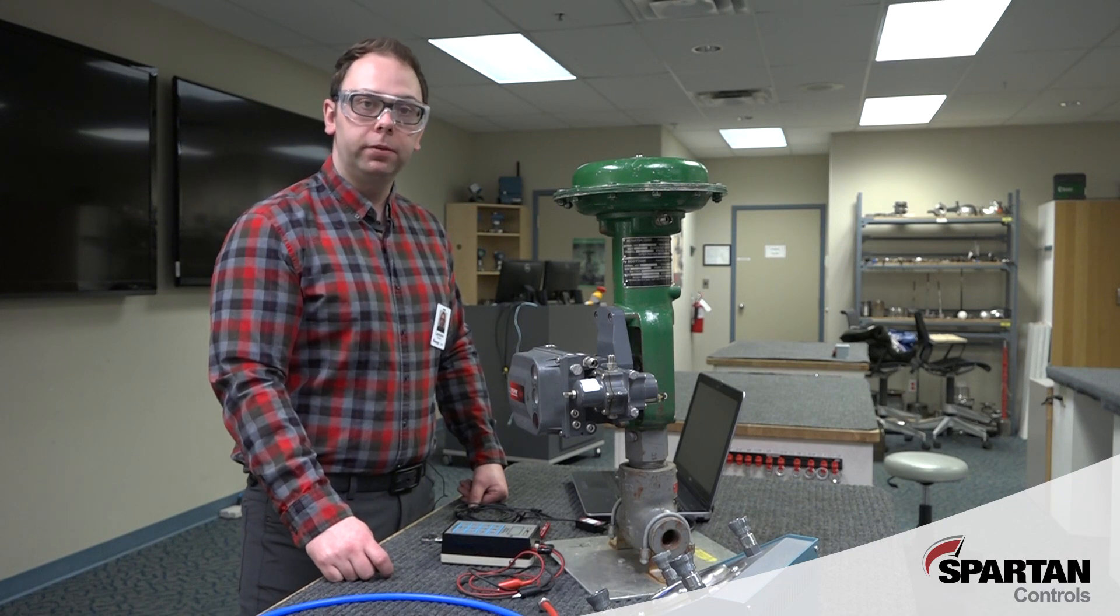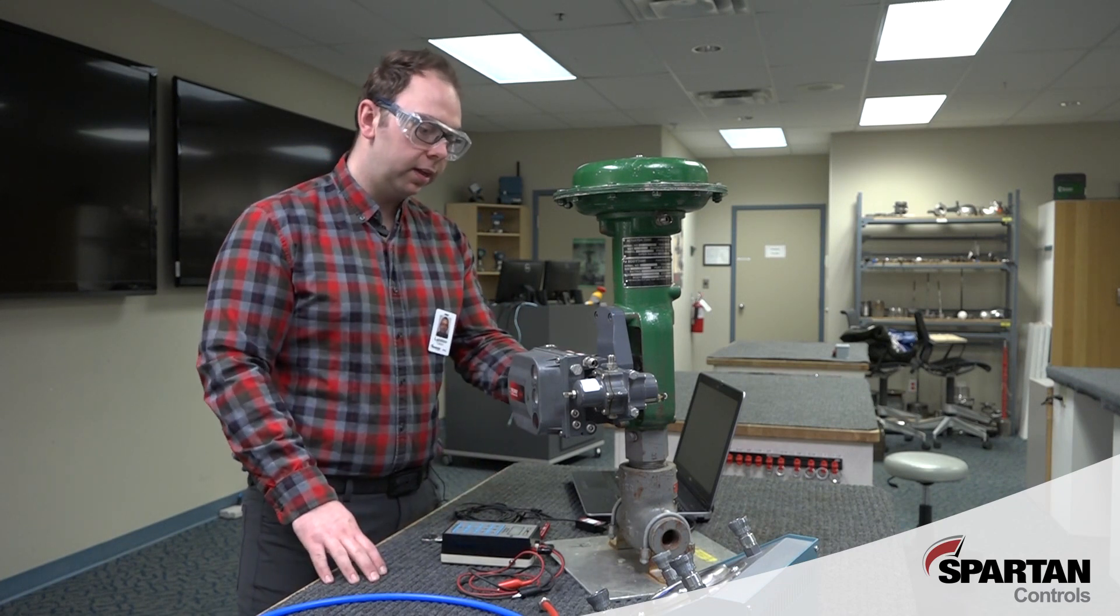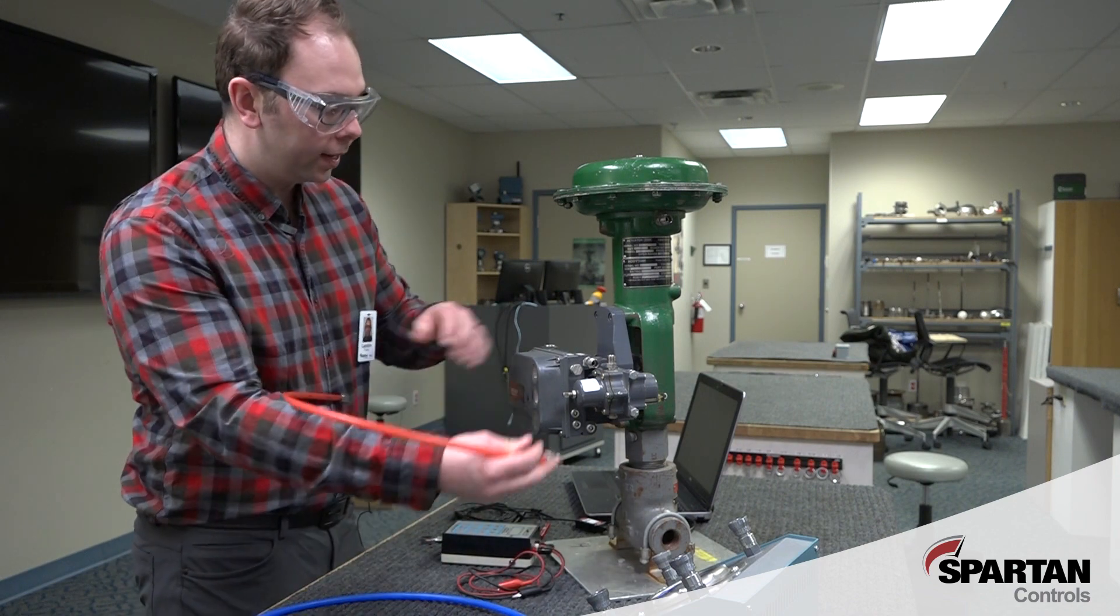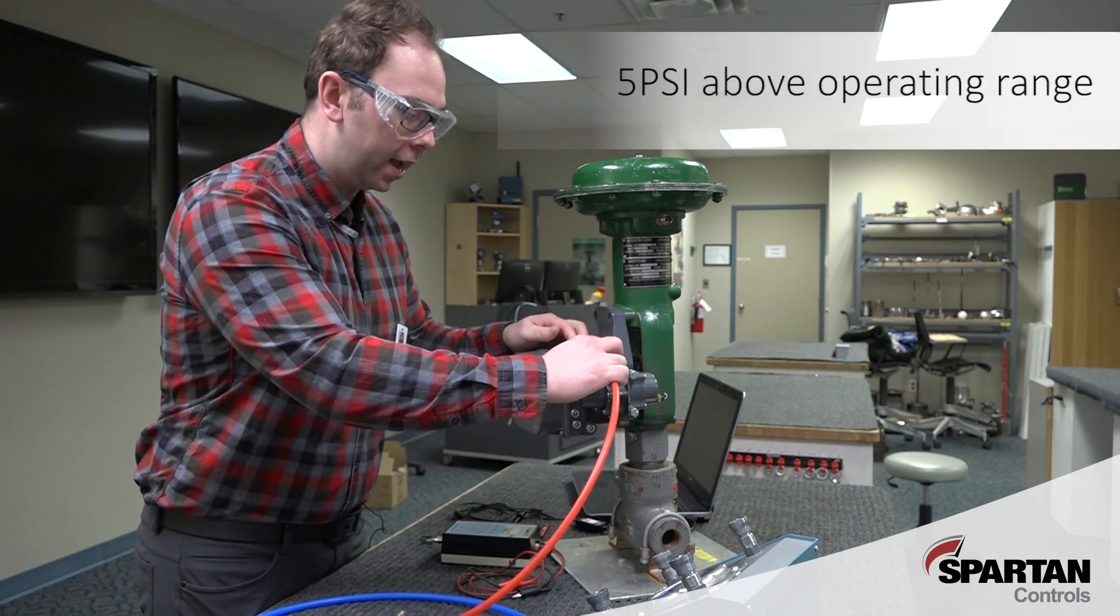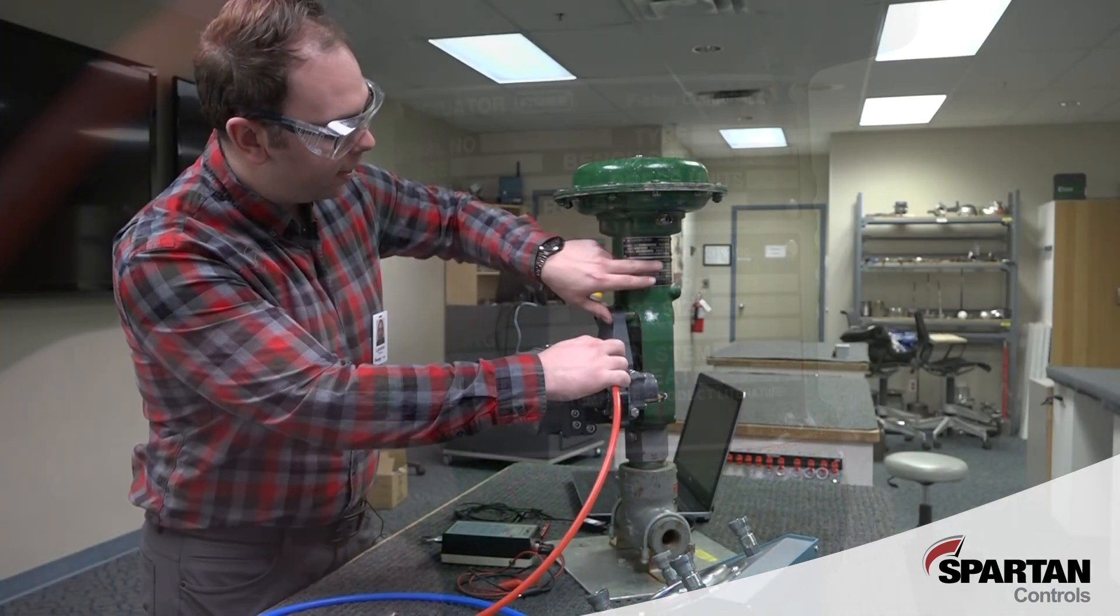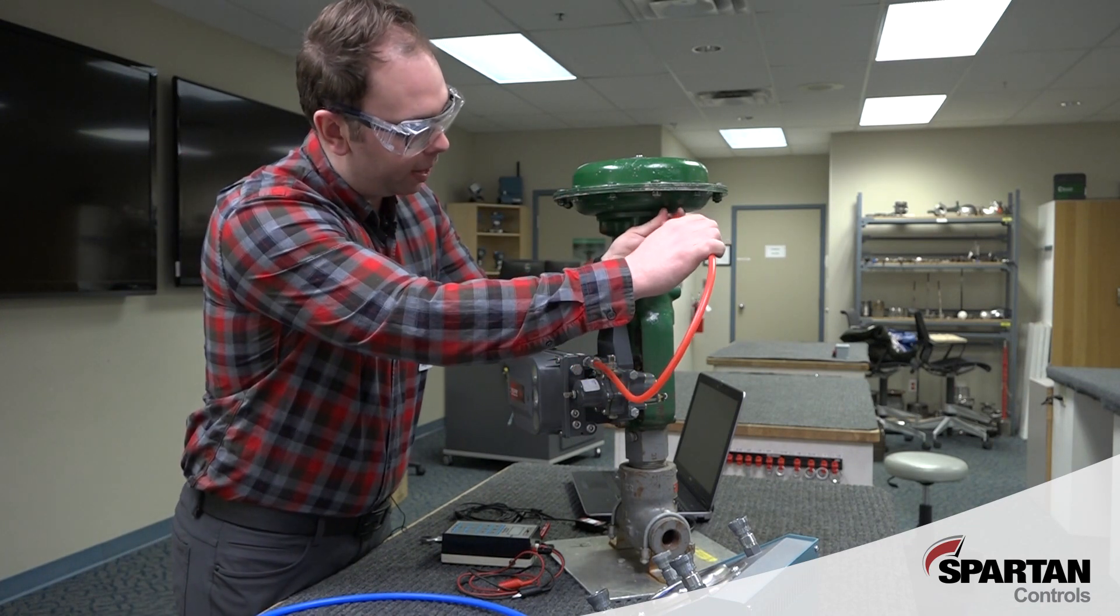Our first step is to ensure that our DVC is mounted correctly and that our feedback arm is lined up. Lastly, we'll need to make sure our airlines are connected and that we have our regulator set 5 psi above our operating range on our actuator. You can find that operating range right here on the nameplate and if you have any questions about mounting your DVC or lining up your feedback arm, there's a link in the description to another video to show you how to do that.